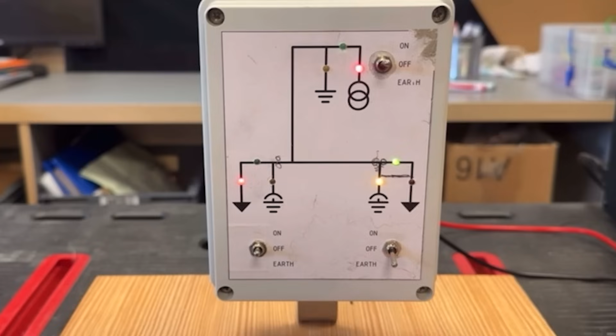Also, on these units, you can put it into what they call earth. So now I could go from on to off and earth. What you do is go to this substation and switch it off, then go to the other end and switch it off, then put it into earth at that end, then put it into earth at this end. Then the cable underground will be off and earth.